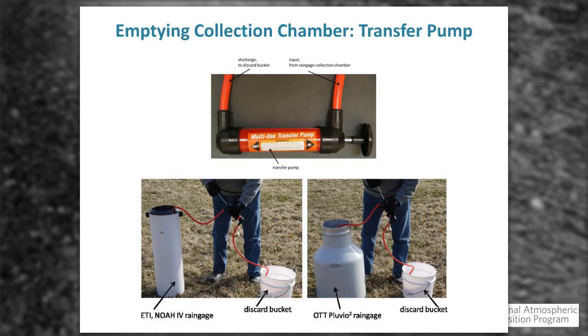Here's the transfer pump — this is what you use when emptying out precipitation or antifreeze after winter. If you do not have one of these, email or call me and we'll get you one ASAP. It's much better than removing the shell off the gauge and trying to pick up the big bucket from the OTT Pluvio to find somewhere to dump it. With the transfer pump you can take it in a discard bucket, cap it, and take it somewhere environmentally friendly for proper disposal.